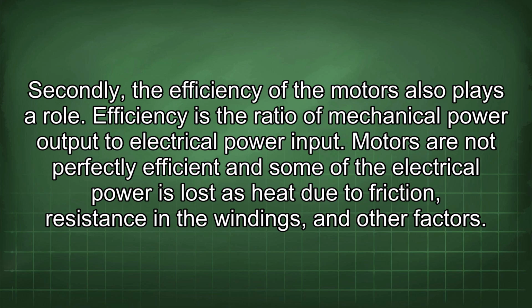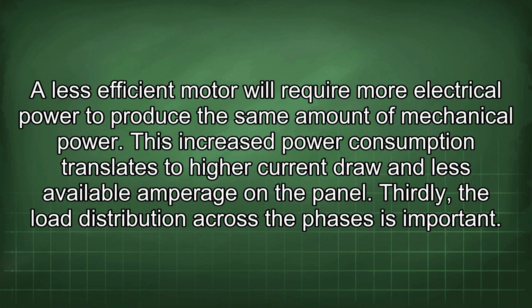Secondly, the efficiency of the motors also plays a role. Efficiency is the ratio of mechanical power output to electrical power input. Motors are not perfectly efficient, and some of the electrical power is lost as heat due to friction, resistance in the windings, and other factors. A less efficient motor will require more electrical power to produce the same amount of mechanical power. This increased power consumption translates to higher current draw and less available amperage on the panel.